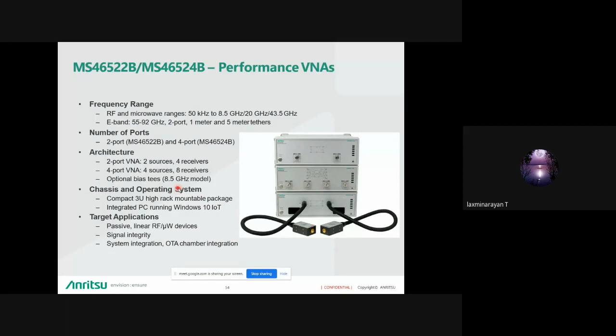Compared to the benchtop, it will be lesser in cost compared to the other competitors or other network analyzers. And it has a 3U package where you can mount it in the ATE setups, and you can use it with a controller. And it also has a 3 years warranty. So the frequency range, as I described, is 50 kilohertz to 43.5 gigahertz with 2 ports, and it is used for passive linear RF and microwave devices, for fast switching speed applications, in signal integrity measurements, and over-the-air chamber testing we can do.